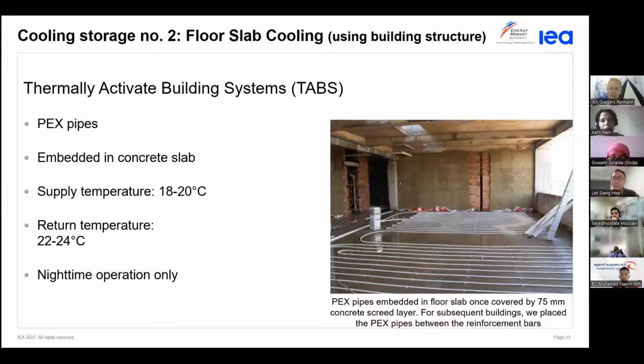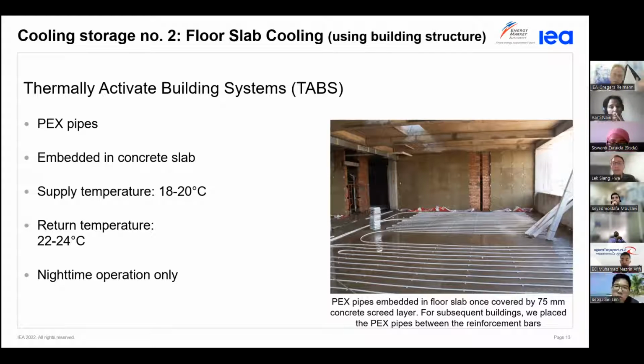So they're basically inside the concrete slab and give cooling both up and down, mostly down actually, because upward there would be a carpet which insulates a bit, whereas downward there's an exposed ceiling, and cold air drops. So they cool the air around the ceiling, which drops down through buoyancy and is replaced by hot air - this kind of convection cell happens automatically. So most of the cooling actually comes from the ceiling in this system.